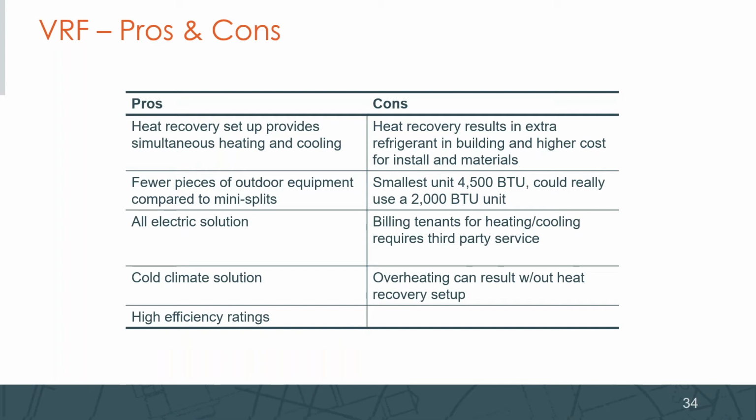And then if you don't set it up with heat recovery, so you're saving that money on the heat recovery loop, your system's going to be in either heating or cooling. You don't get to choose. So October 1st, your building gets changed over to heating, and you're still heating up in your apartment because it's super insulated, airtight, and you're on the south side, and you have 3 people in your house having a party, and you're going up into 85-degree territory. You can't turn your cooling system on. It will not come on. You're only in heating mode. So that is an issue in our airtight, Passive House, high-performance buildings.